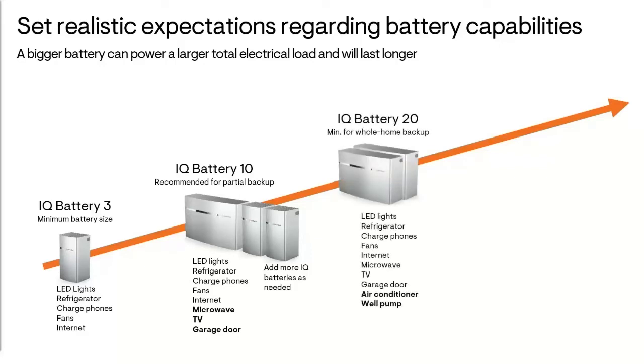For whole home backup, or if any large electrical appliances require backup power, at least 2 IQ battery 10s should be installed. A large electrical appliance is one that connects to a 30 to 40 amp double pole circuit breaker, or potentially larger than that. Typical examples are air conditioners, pumps, and large kitchen appliances like cooktops and ovens.